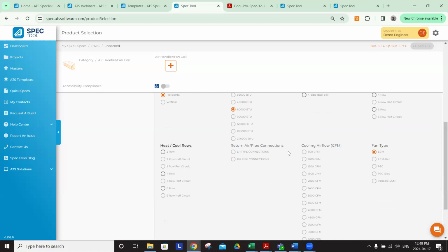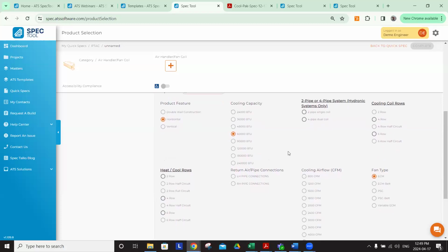So the only options that we have left in these units are about how many coil rows we actually need. The 2-pipe or 4-pipe system is one that you can do fairly quickly as well. You'll know if your building is doing a full hydronic system and then a separate chilled water system, or if you're doing a single hydronic system in the building that's going to be switched from heating to cooling seasonally, then you can choose 2-pipe. Usually, especially in these units, it's a 4-pipe system so that they can do what they need to do regardless of the season. So yeah, we'll choose 4-pipe.